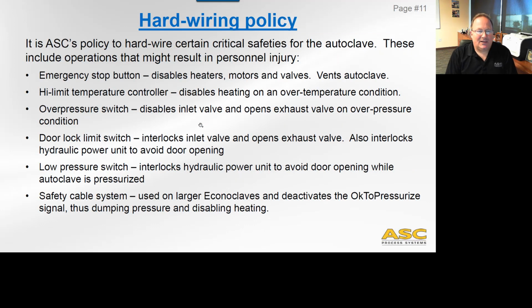So let's talk about hardwiring policy. It is ASC's policy to hardwire certain critical safeties for the autoclave. These include operations that might result in personal injury. So basically, we don't hardwire every type of interlock on the control system. We only focus on those things that might result in personal injury, and that's an important distinction. So the first is the emergency stop button. That is where an operator tries to hit a button and he wants everything to stop. So that's going to disable heaters, motors, valves, and it'll also vent the autoclave.